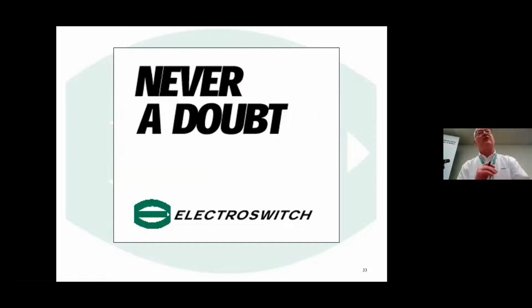The most common utility switch types are definitely the lockout relay, the ANSI 86 relay, and then there's a function called the 43 switch. It's a local remote switch, so that could be a selector switch for local and remote operation.